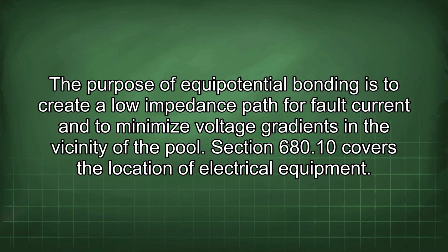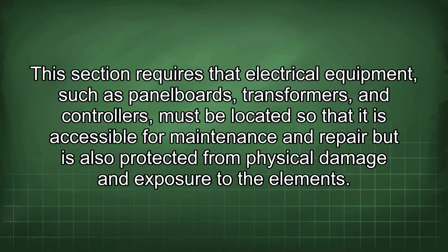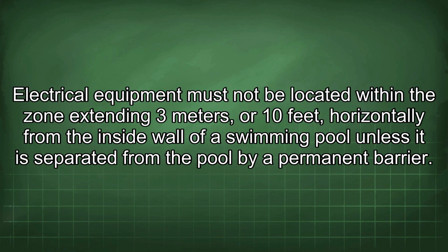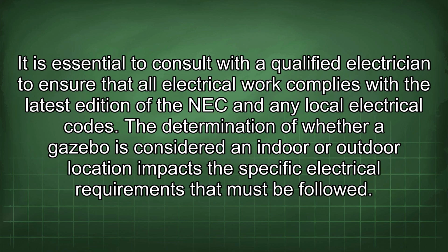Section 680.10 covers the location of electrical equipment. This section requires that electrical equipment, such as panel boards, transformers, and controllers, must be located so that it is accessible for maintenance and repair but is also protected from physical damage and exposure to the elements. Electrical equipment must not be located within the zone extending 3 meters or 10 feet horizontally from the inside wall of a swimming pool unless it is separated from the pool by a permanent barrier. It is essential to consult with a qualified electrician to ensure that all electrical work complies with the latest edition of the NEC and any local electrical codes.